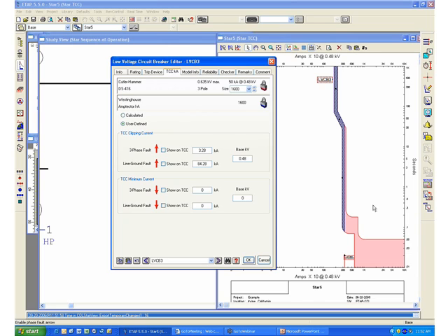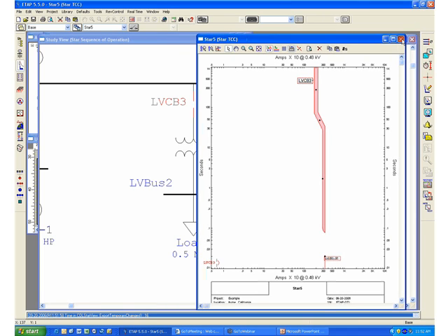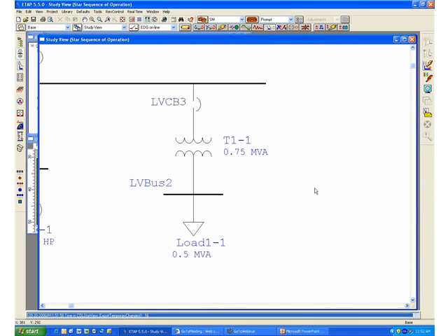Therefore, the program automatically determined that you could potentially have a very high clearing time, and it has flagged that automatically.